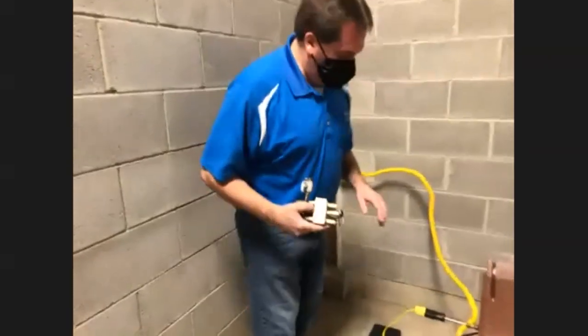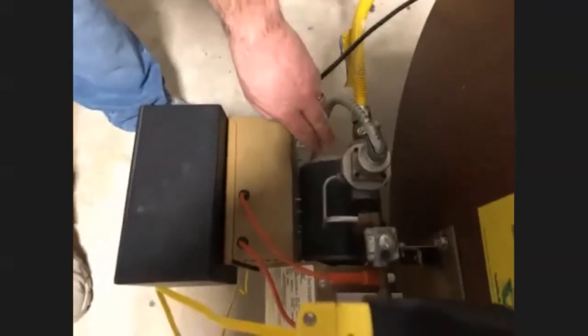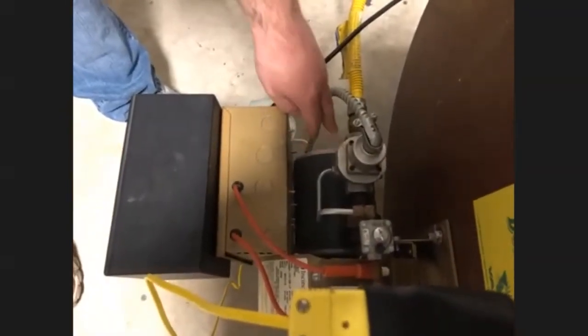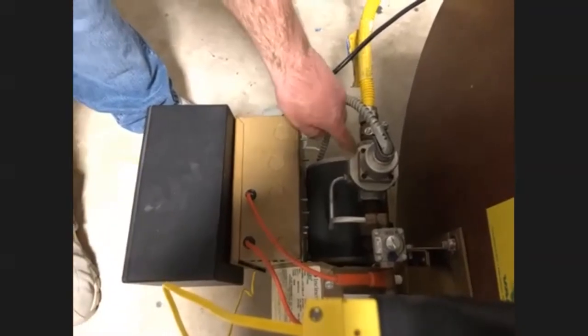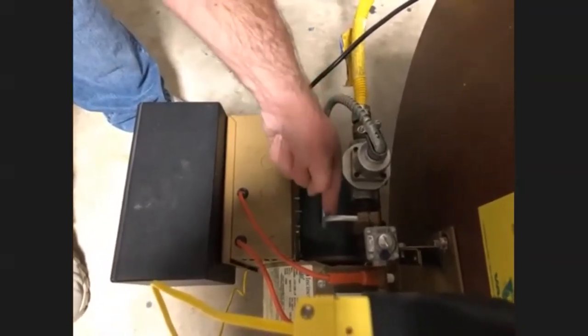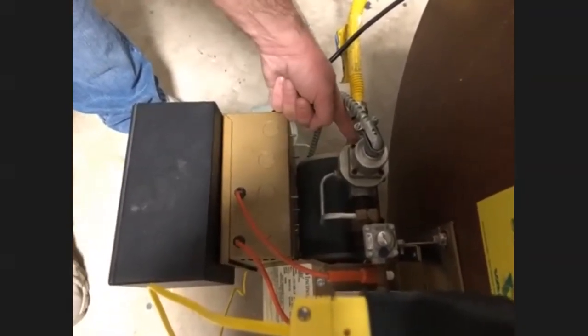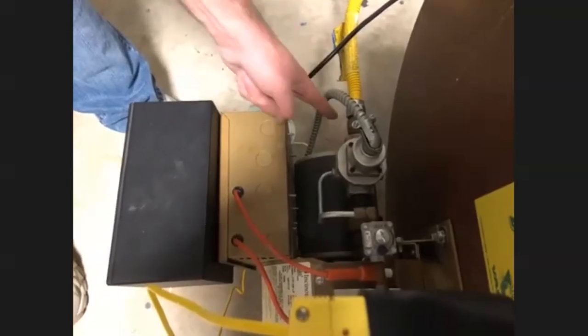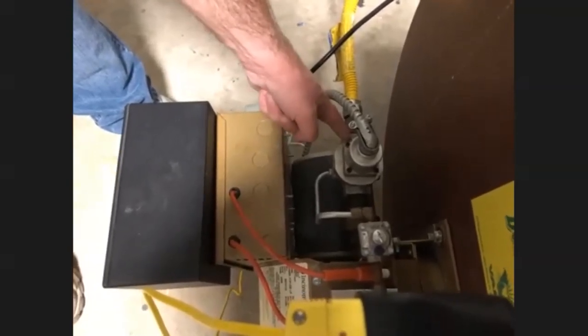What you can do on the gas burners is check your main input regulator. For natural gas, you want to have 5 to 5.5 inches coming into the regulator. If you're running propane, you want 11 inches coming into the regulator. And you need to check that at your main regulator coming from your fuel supply.